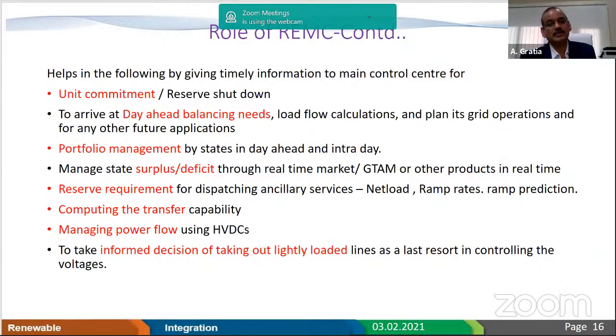When solar capacity grows—currently around 100 gigawatt target, moving toward 300 gigawatt—at around 70% PLF that could mean 200 gigawatt, which is huge, since solar power comes in between 7 and 9 and goes out between 4 and 6 in the evening. That amount of power has to be managed properly, with load-generation balance maintained. Further reserve is required, and unit commitment will be needed for conventional thermal and hydro generators. This is the advice REMC gives to the other load dispatching schemes.